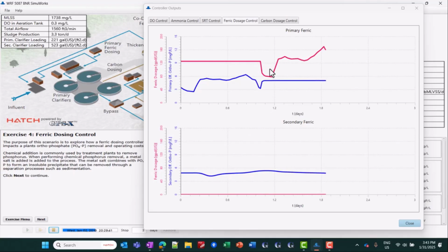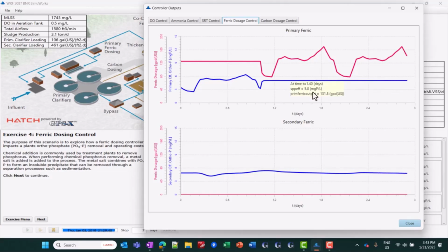We can see the controller making dynamic changes to the amount of chemical being dosed in response to the phosphorus. It's maintaining 5 milligrams per liter phosphorus out of this dosing point, doing the job of removing phosphorus in a very dynamic way, so we have very stable phosphorus there.